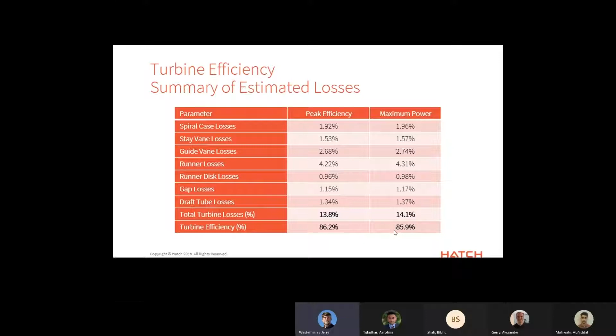We look at the peak efficiency point, and also the maximum power condition. In this case, the peak efficiency is only slightly higher than the maximum power condition. As turbine efficiencies go, this isn't a very high efficiency. We'd expect a larger station to have something well into the 90s, so yeah, this isn't very good.